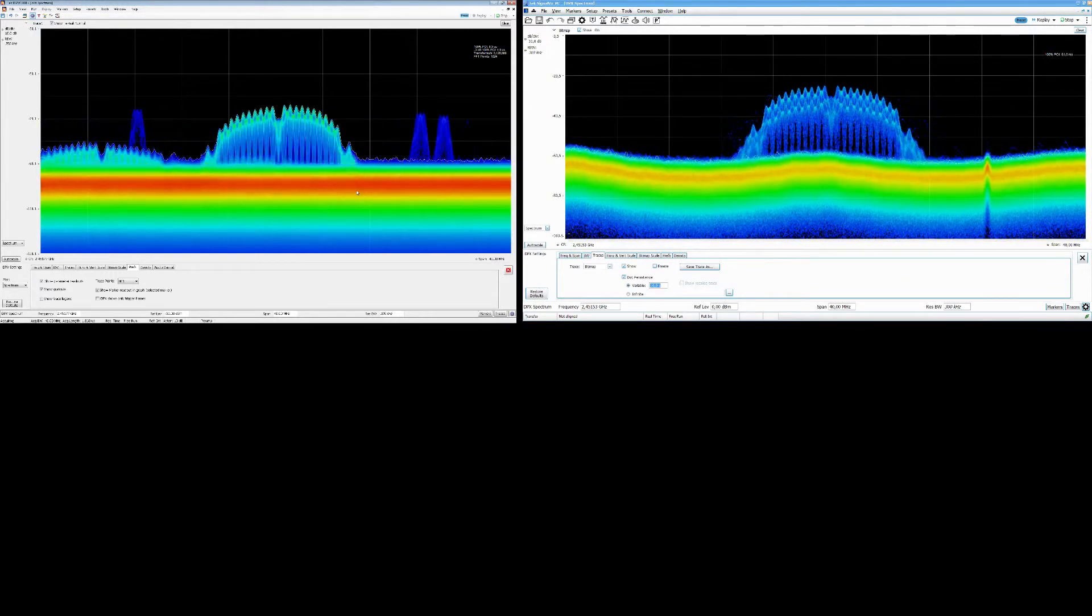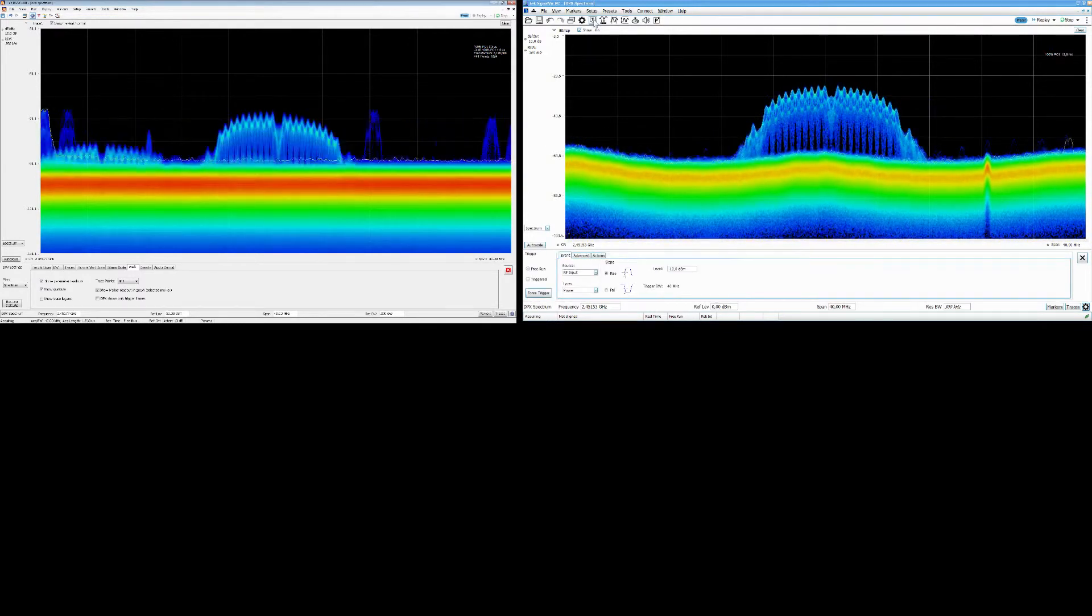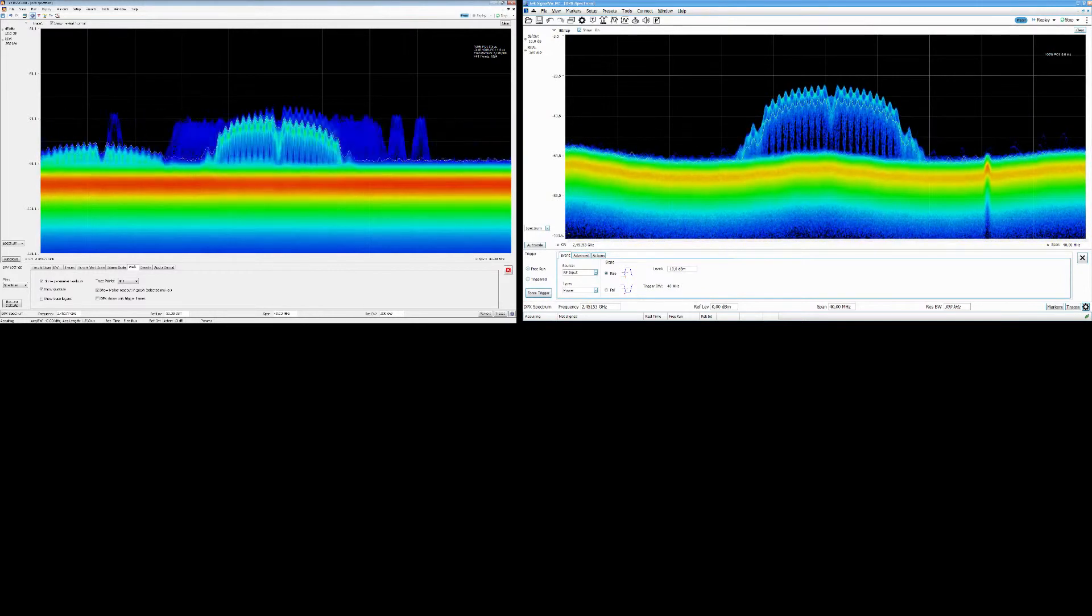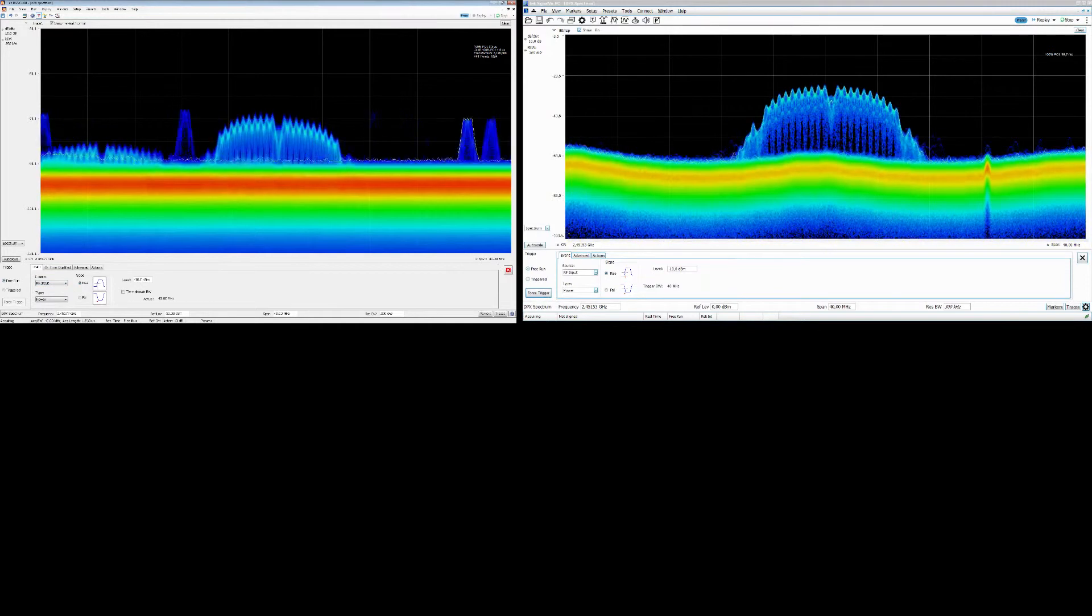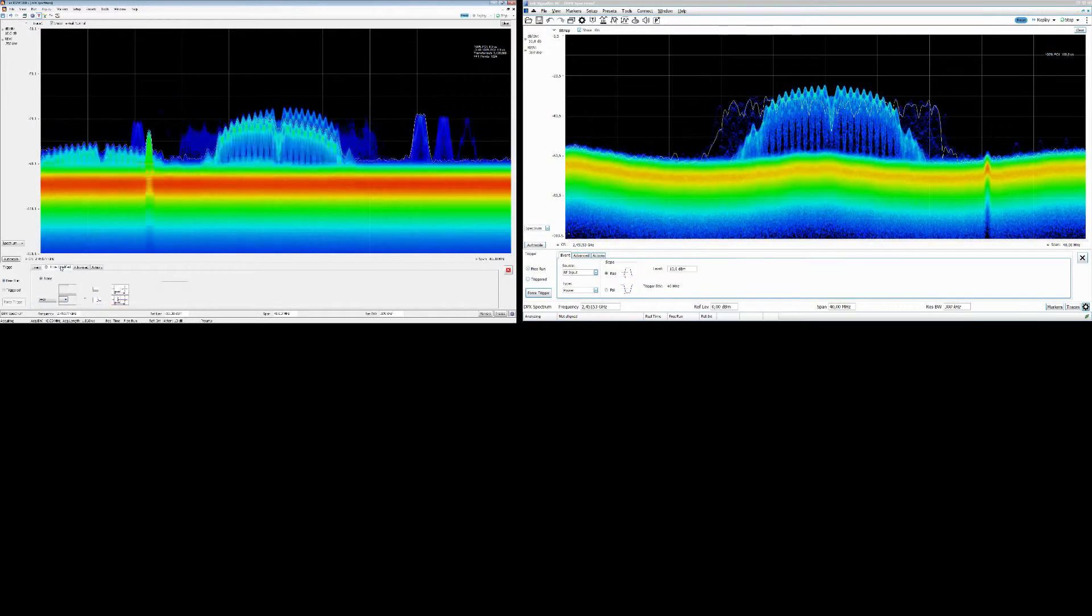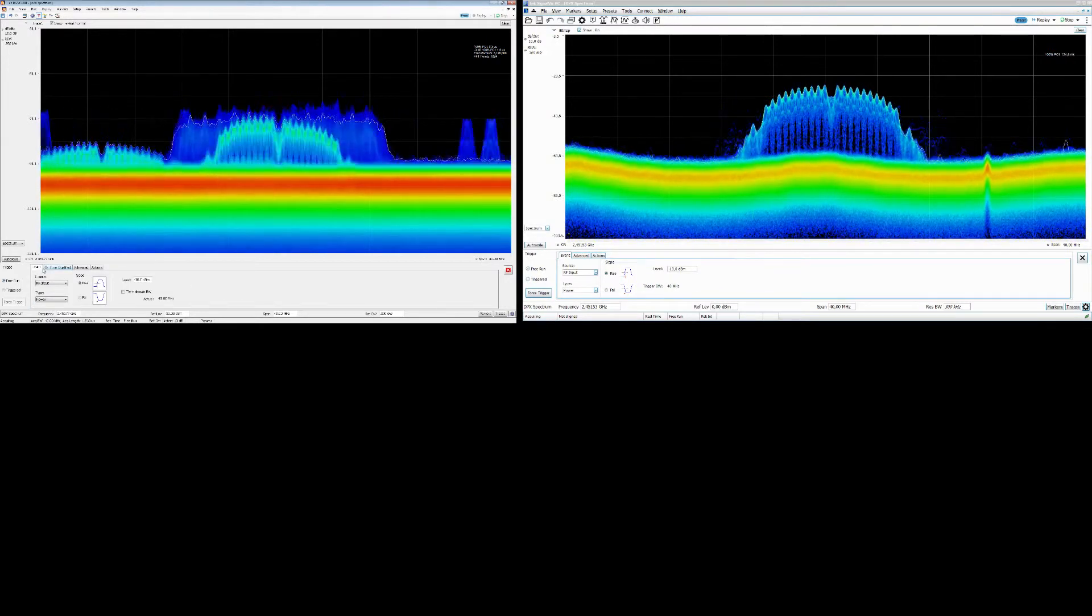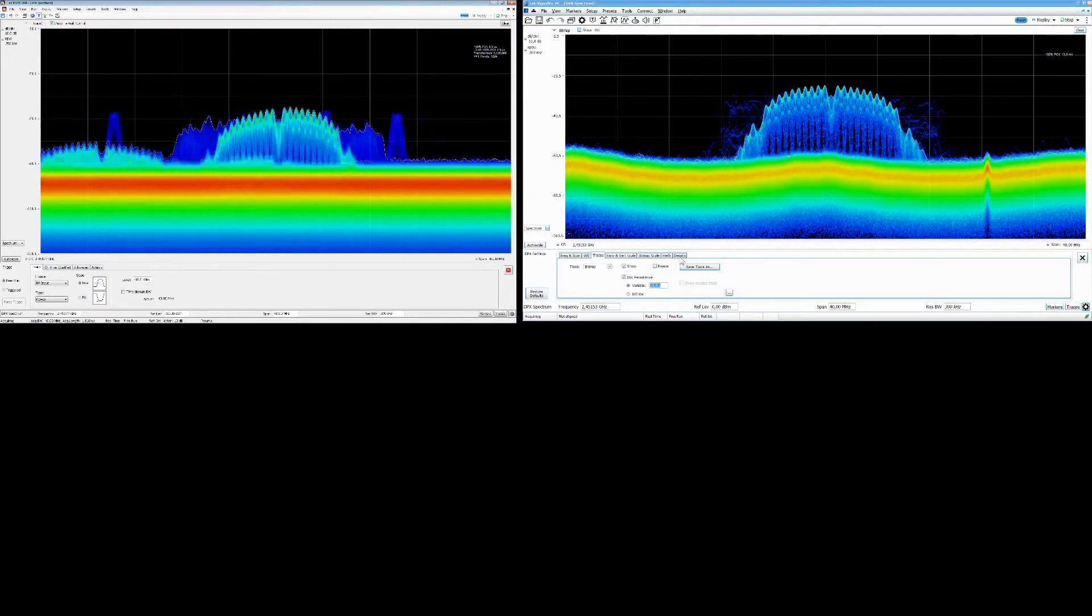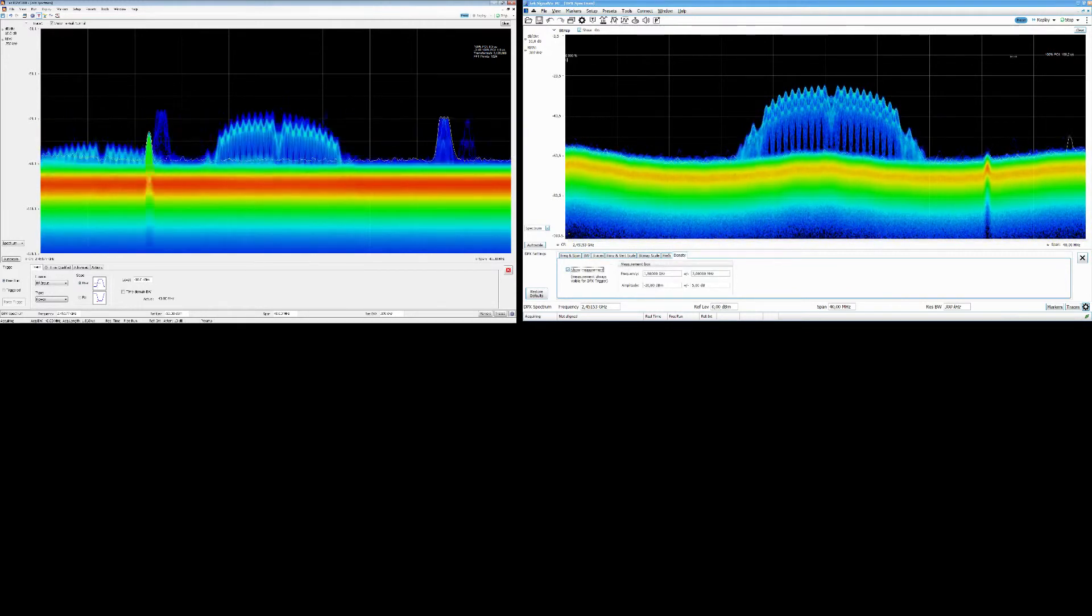The last thing you can do here which is also really unique is all the trigger functionalities. If you've been here to the trigger menu, it's like the trigger, so bandwidth always 40 megahertz, and you can just level trigger. If you go to the trigger on this one, you have RF input, you have power, but you also have frequency mask, density, and runt, and there is also qualification. So there's a little bit more trigger capabilities.